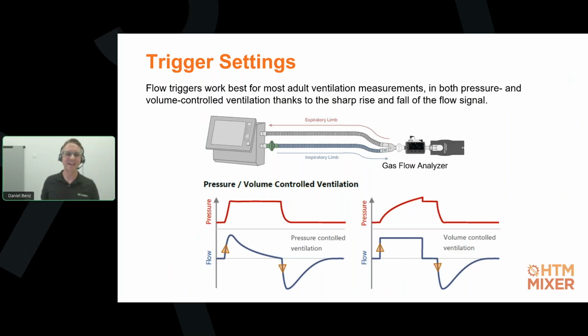Okay, and that doesn't surprise me, because the good news is the most modern gas flow analyzers have default trigger sets for example for adult, pediatric applications and high frequency ventilator testing. These triggers will work well in, I would say, 90 to 95% of your applications. It's specifically always where you have a positive and negative flow through the flow channel of your analyzer.